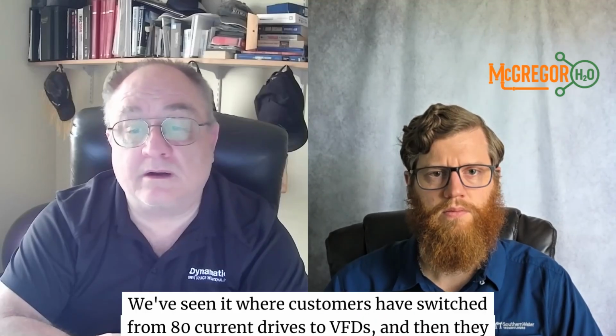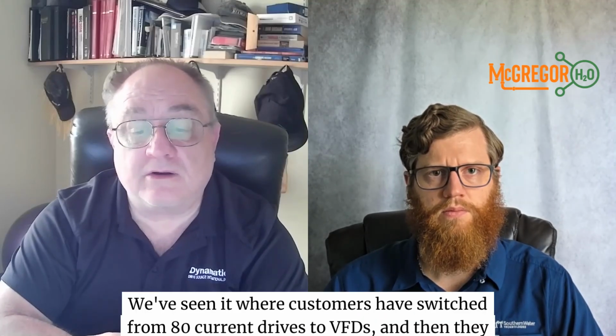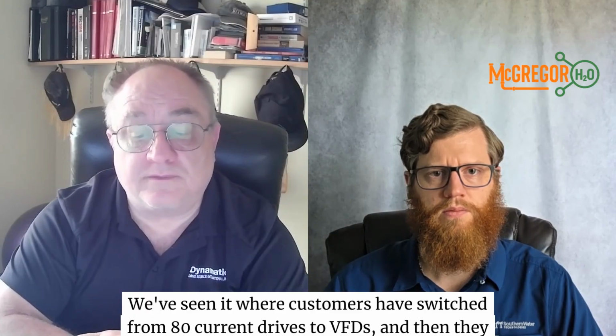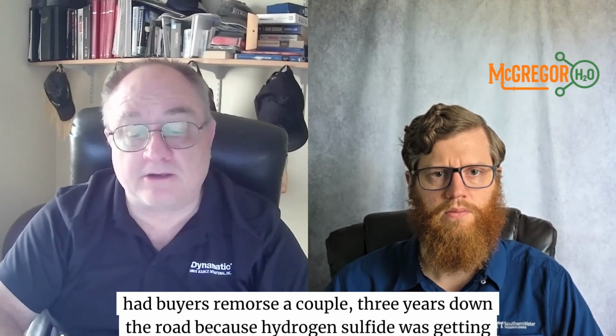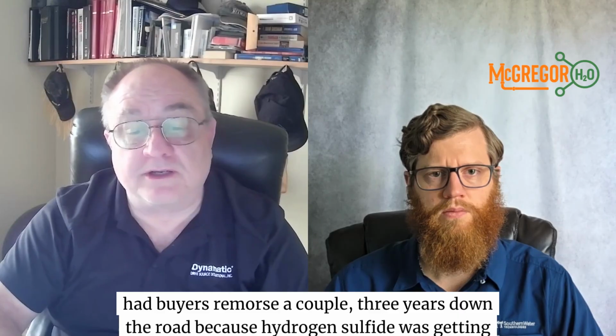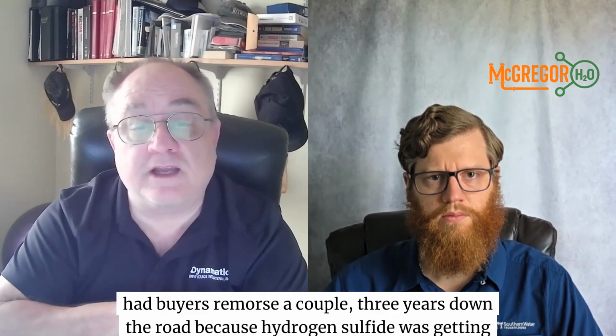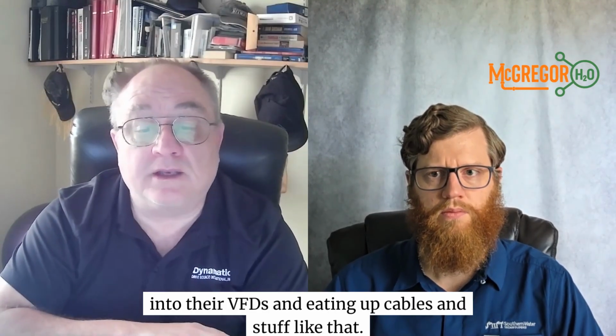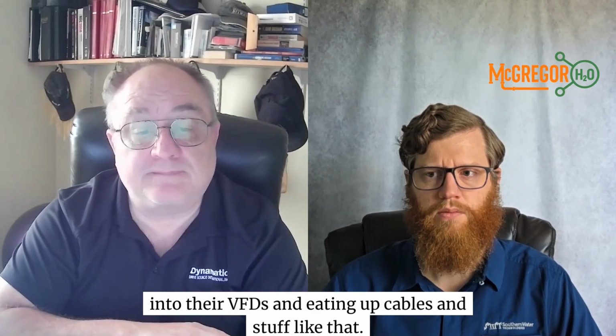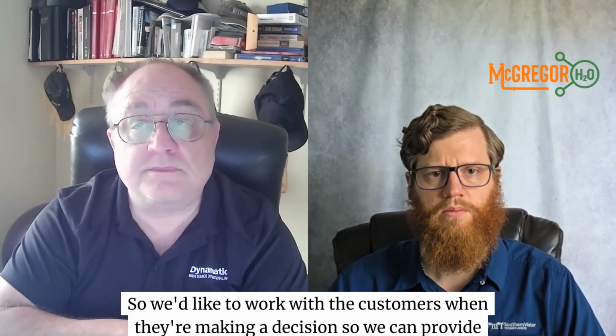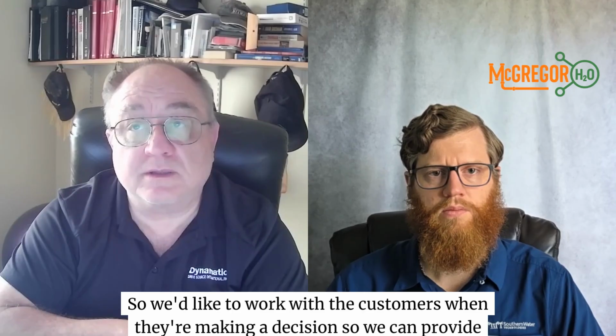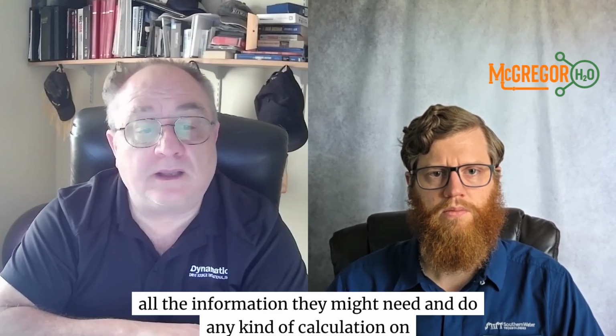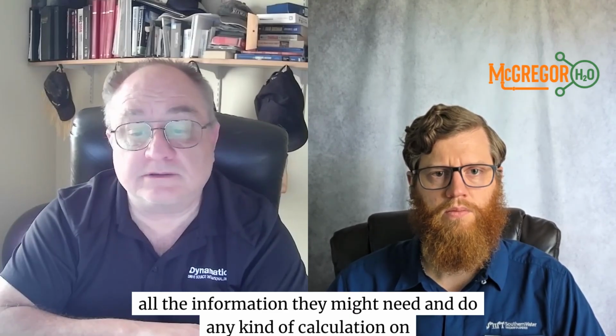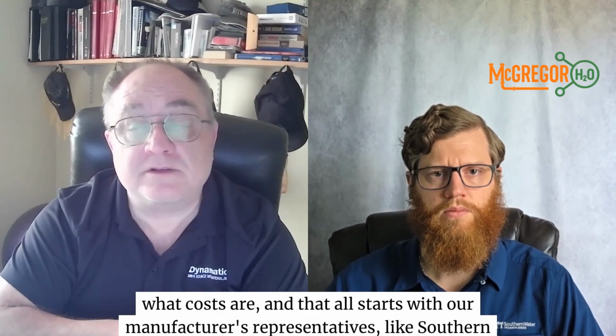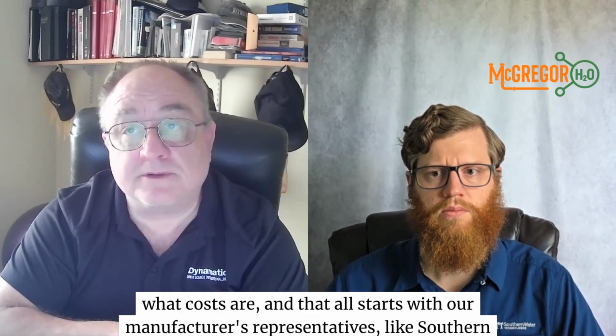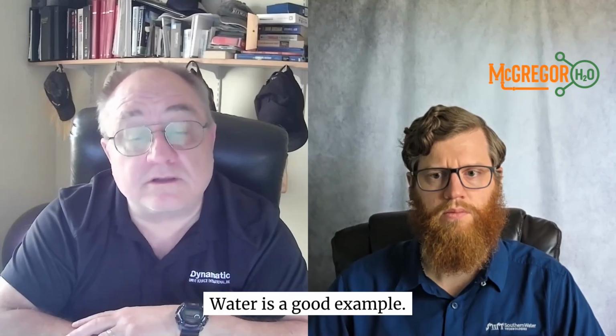We've seen it where customers have switched from eddy current drives to VFDs, and then they had buyer's remorse a couple, 3 years down the road because hydrogen sulfide was getting into their VFDs and eating up cables and stuff like that. So we'd like to work with the customers when they're making a decision so we can provide all the information they might need and do any kind of calculation on what costs are. And that all starts with our manufacturer's representatives, like Southern Water is a good example.